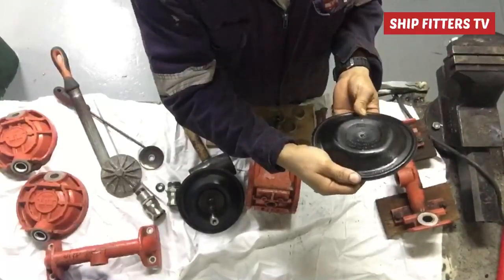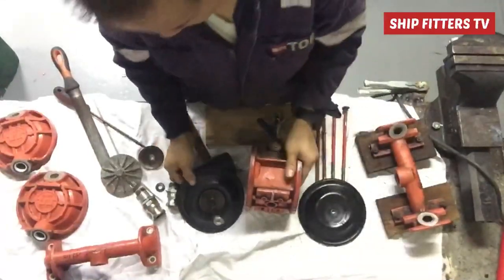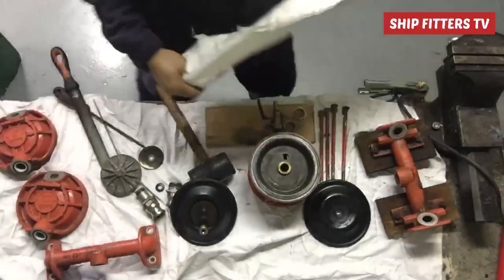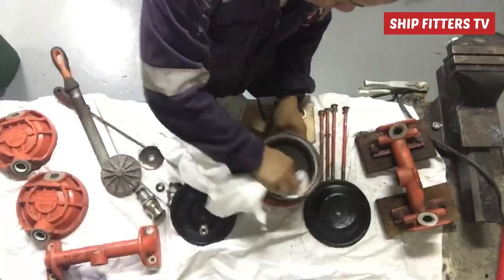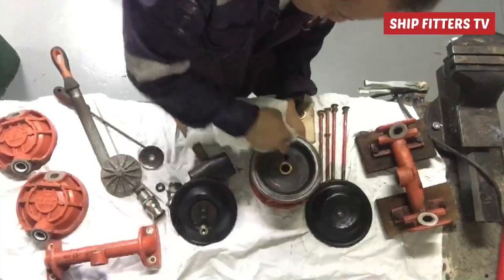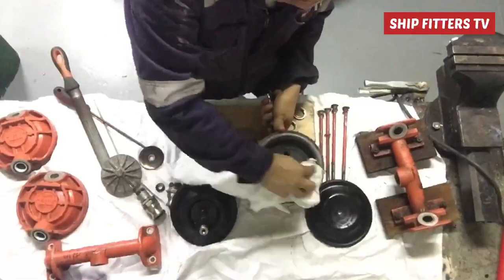How does the air-operated double diaphragm work? This Wilden pump is a double diaphragm type. A double diaphragm is a positive displacement pump which utilizes two flexible diaphragms that reciprocate back and forth, creating a temporary chamber that draws and expels fluid through the pump. That is how the double diaphragm works.